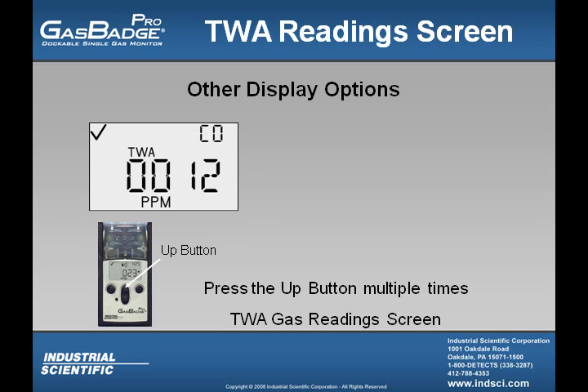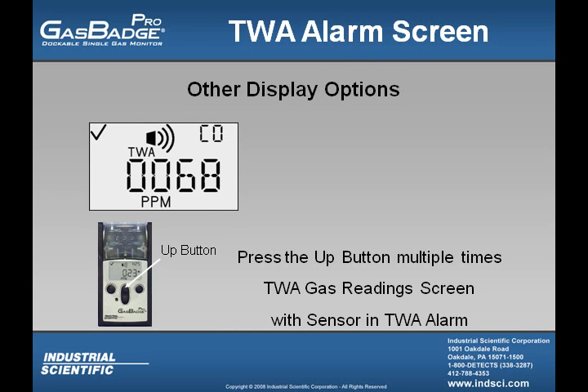The GasBadge Pro also records the time-weighted average. The user can view the time-weighted average by pressing the Up button multiple times until TWA is shown, just like the one shown in this screen. If the time-weighted average is exceeded, then the GasBadge Pro will go into a TWA alarm mode. If the user wants to check this screen, they can again press the Up button multiple times until they see this screen, shown with the alarm indication as well as the letters TWA.